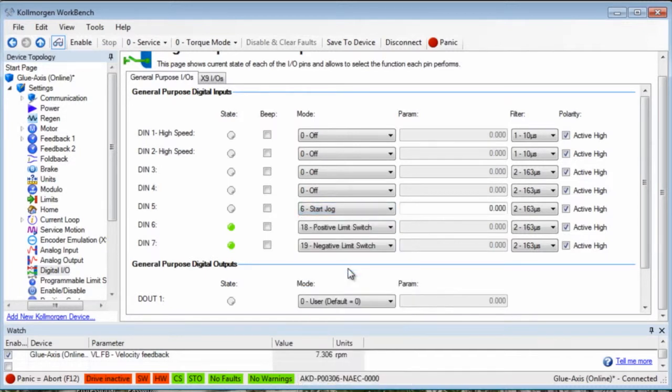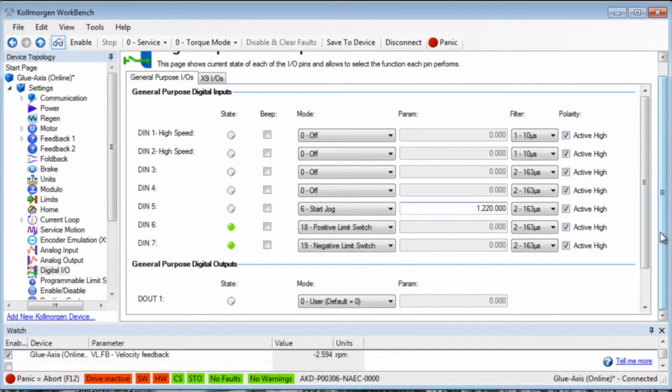Input 5 is set to mode 6, start jog, and the param area becomes available. The param will be set to the jog speed desired. The filter can be adjusted if desired, and the switch polarity inverted as well.